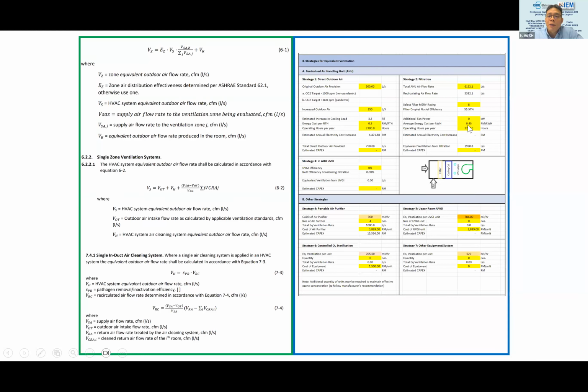But the MVC is based on strategies, so if you have different strategies, you add up the equivalent outdoor air of each strategy. When you come to the AHU though, we follow the same format because we minus off -- when you have UVC with a filtered air versus UV without the filter, the efficiency is different. You need to minus out the flow rate that goes through the filter, multiplied by the efficiency. So this is all arithmetic. If you follow the air path it's more systematic for the designer, but for a layperson style, the MVC is still very useful.